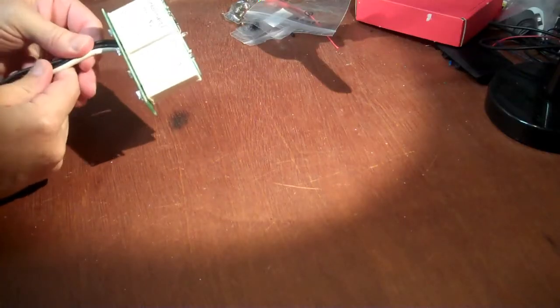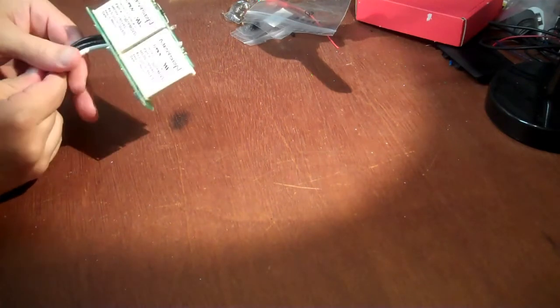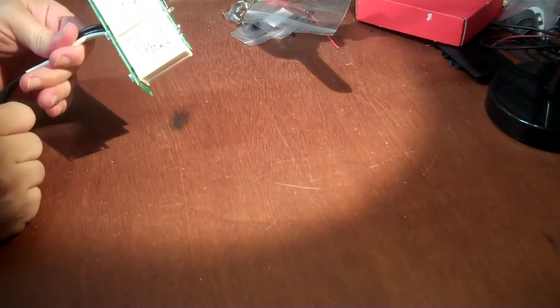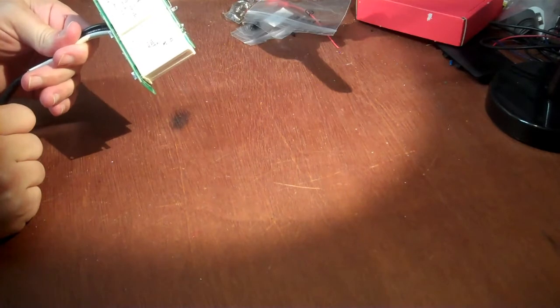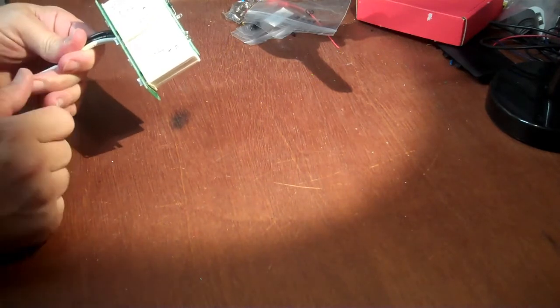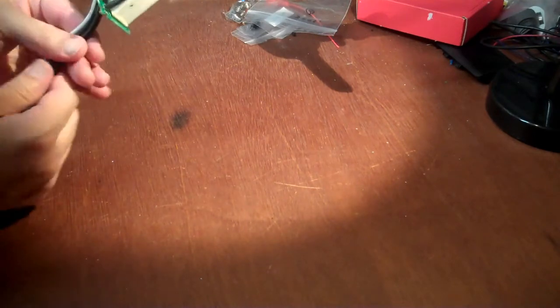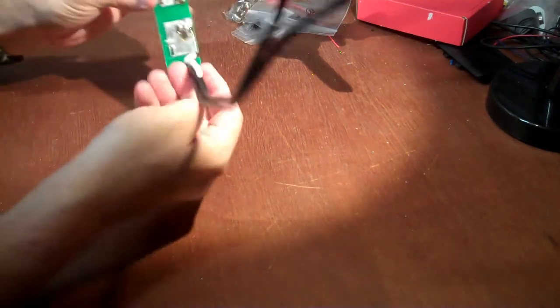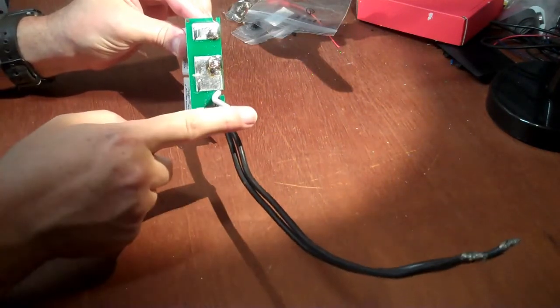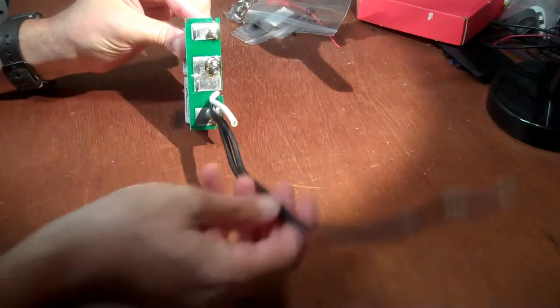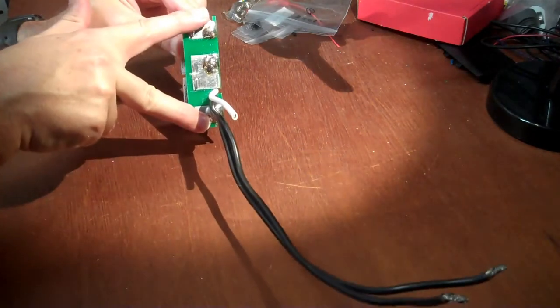All right, there we go. So what's inside this surge arrestor is quite simple. There's two of these and that's what does all the work. They're MOVs, thermally protected MOVs, which is a metal oxide varistor. And essentially, if you look at how they're wired up, you have the neutral line going to the center and your two hots going to either side here.